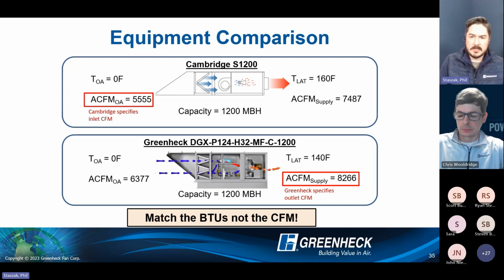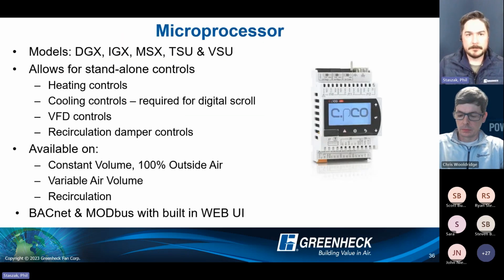That is why we're still slightly higher on the airflow, but slightly higher airflow means slightly higher air changes, as well as a little bit longer runtime to satisfy that space condition, but also provides a little bit more fresh air ventilation to that space. And 140 is going to climb to the ceiling a little bit slower than 160 degrees. But otherwise it's pretty much 1-for-1. BTUs again are basically BTUs in the end. Don't get too confused by what it looks like on paper.